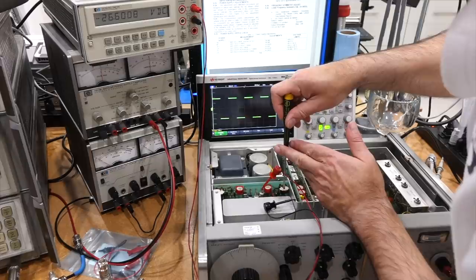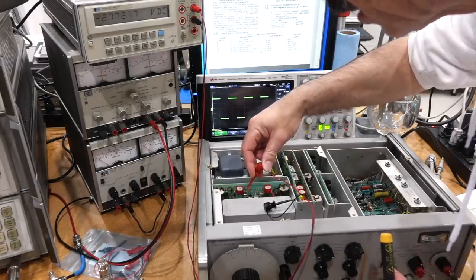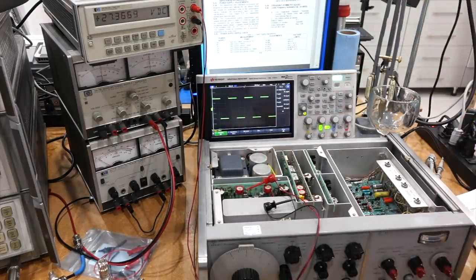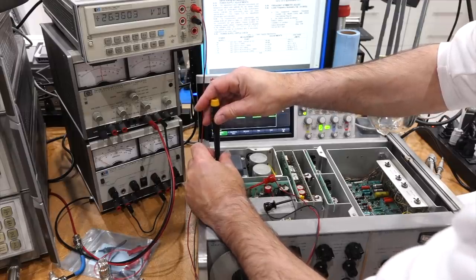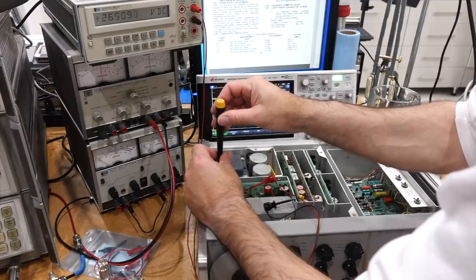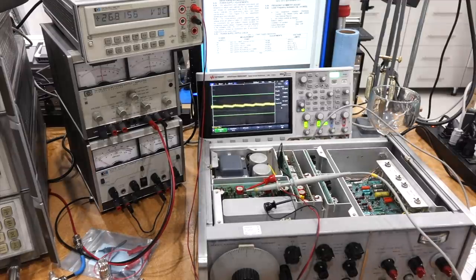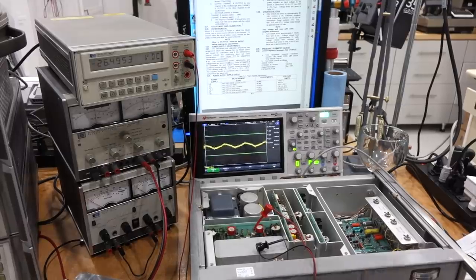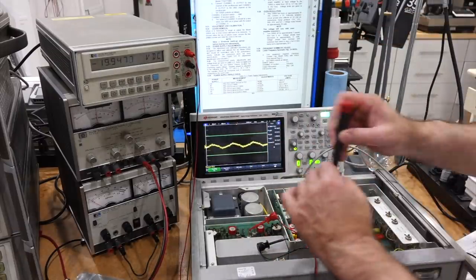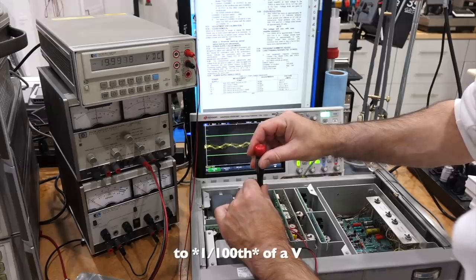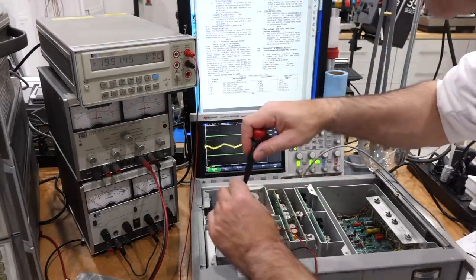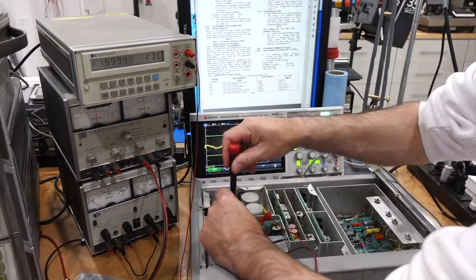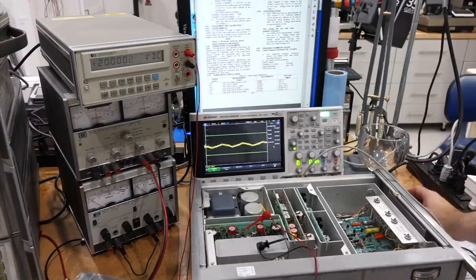This one, and that's 27.3. This is completely off. Had been inspected but not adjusted. 26.5. Okay, it's dancing a little. I'm going to check it at the scope, see if I have any ripple. Nope, that looks good. Okay, we got our 26.5 eventually. And then minus 20 volts first, and then plus 20 volts second. And that they want to a tenth of a volt. Okay. So we got it. We got our power supplies.